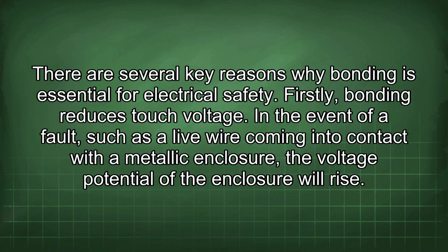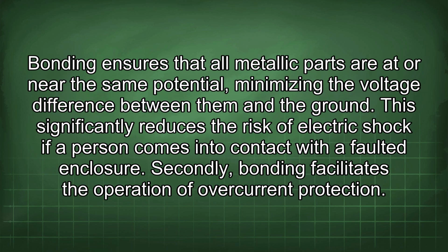Firstly, bonding reduces touch voltage. In the event of a fault, such as a live wire coming into contact with a metallic enclosure, the voltage potential of the enclosure will rise. Bonding ensures that all metallic parts are at or near the same potential, minimizing the voltage difference between them and the ground. This significantly reduces the risk of electric shock if a person comes into contact with a faulted enclosure.